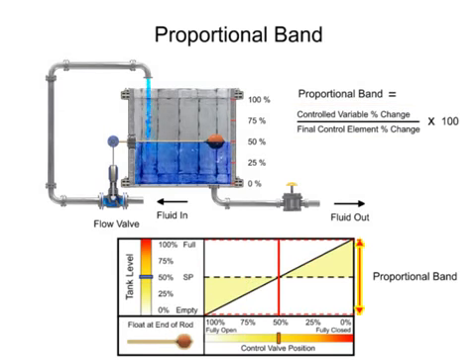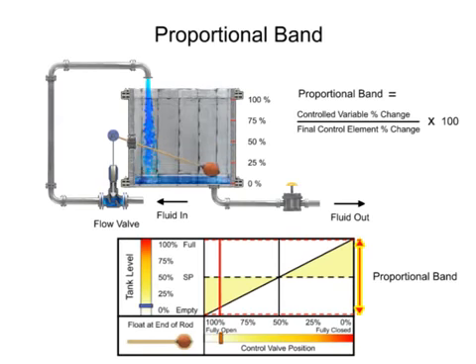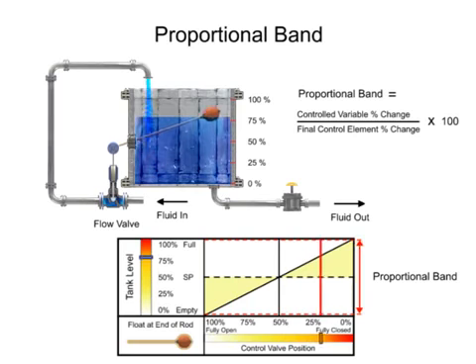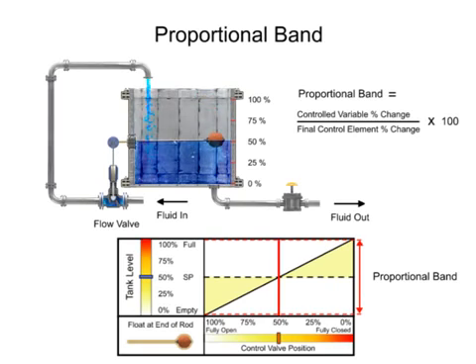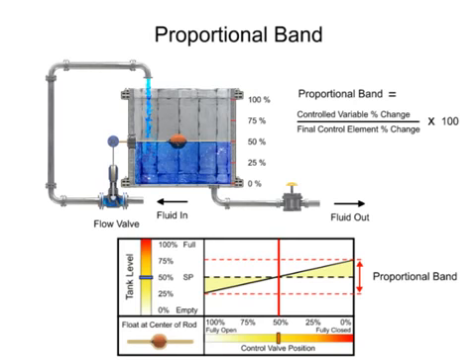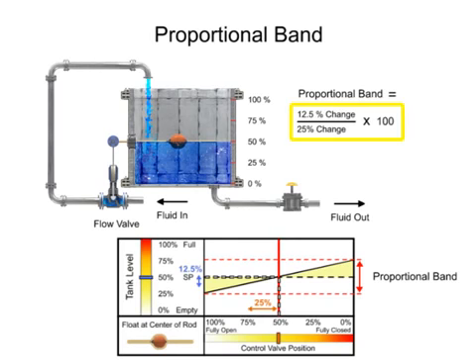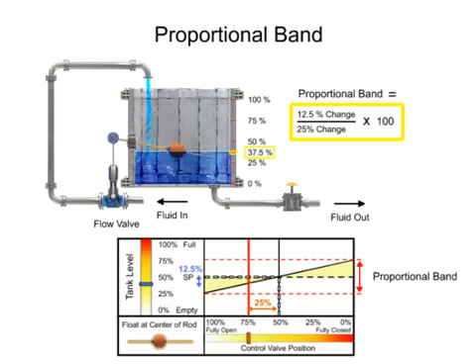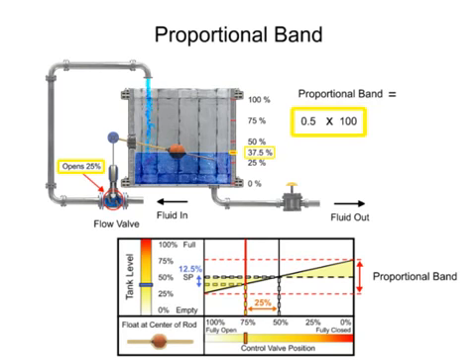The width of proportional band determines how much of a controlled variable change is required to cause the final control element to move by a determined amount. By placing the float on the end of the rod, the fluid level has to change 100% to cause the final control element to change 100%. By placing the float at the center of the rod, the fluid level has to change 12.5% to cause the final control element to change 25%. The width of the proportional band is reduced by half.